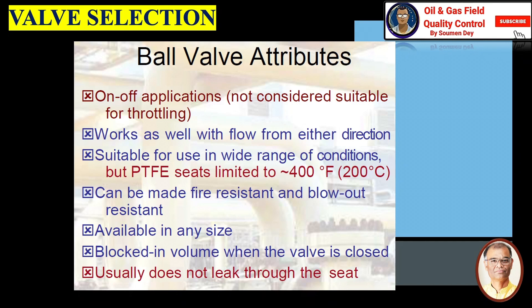Ball valve is the most popular valve used for isolation purpose and on and off applications. Not considered suitable for throttling, works well with flow from either direction. Suitable for use in a wide range of conditions, but PTFE seats are limited to a maximum of 200°C (400°F). Can be made fire resistant and blowout resistant. Available in any size, blocked-in volume when the valve is closed, and usually does not leak through the seat.